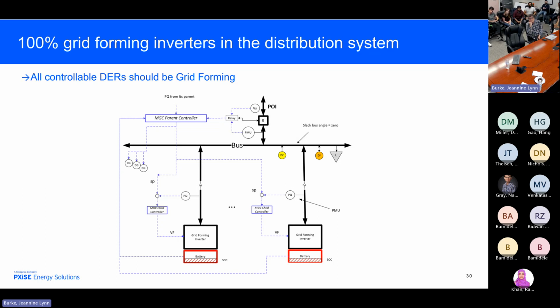This can be done with a simple two-level controller. Remember, I said all the control software is the same. This is a PQ controller, and it's sending VF commands. This is a PQ controller sending VF commands. Now, what happens when you're sending VF to a grid-forming inverter? It's going to cause real and reactive power to flow. As soon as the real and reactive power get to the set point, the error signal is zero, and the voltage stays at its nominal voltage set point, and the frequency goes to its nominal frequency, 60 hertz.